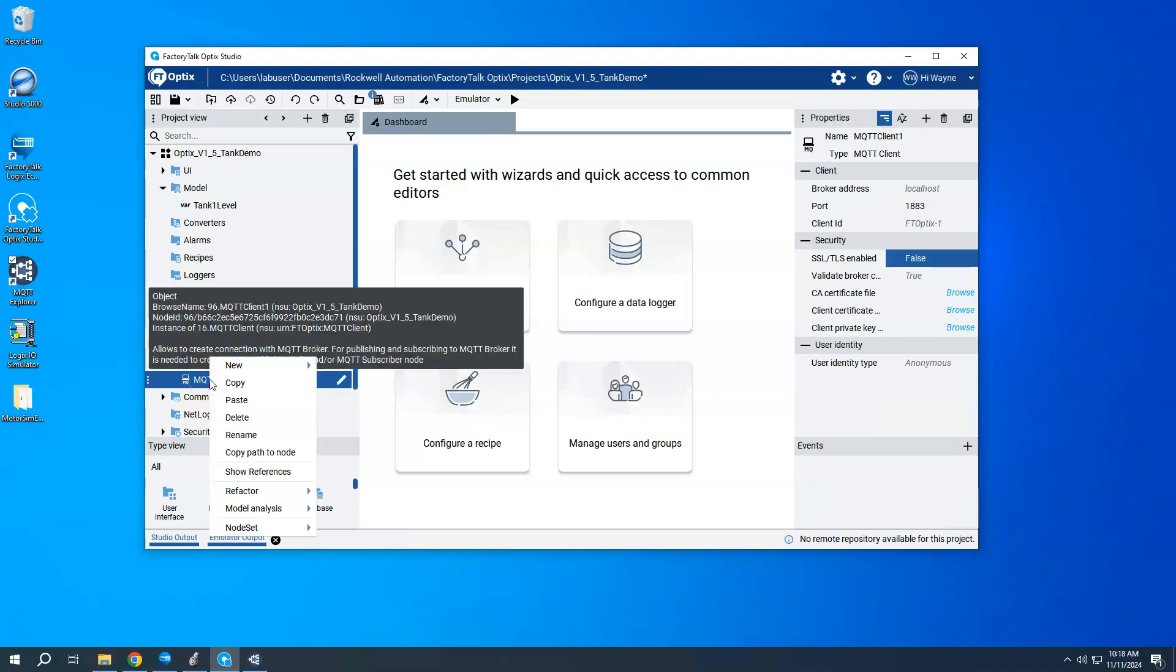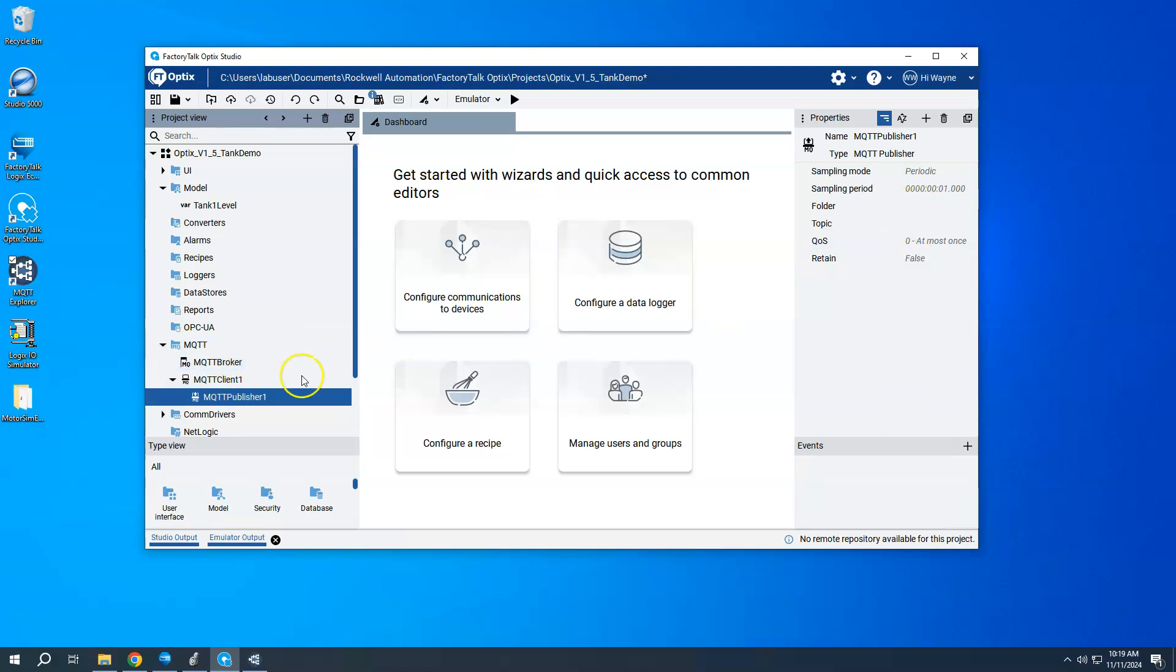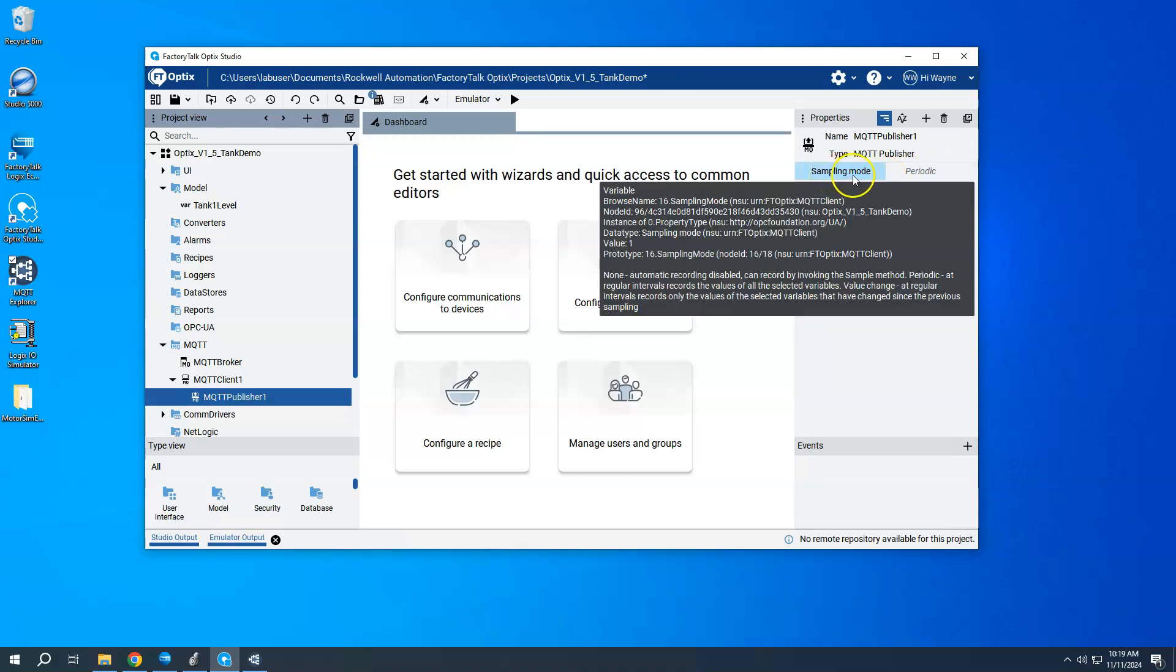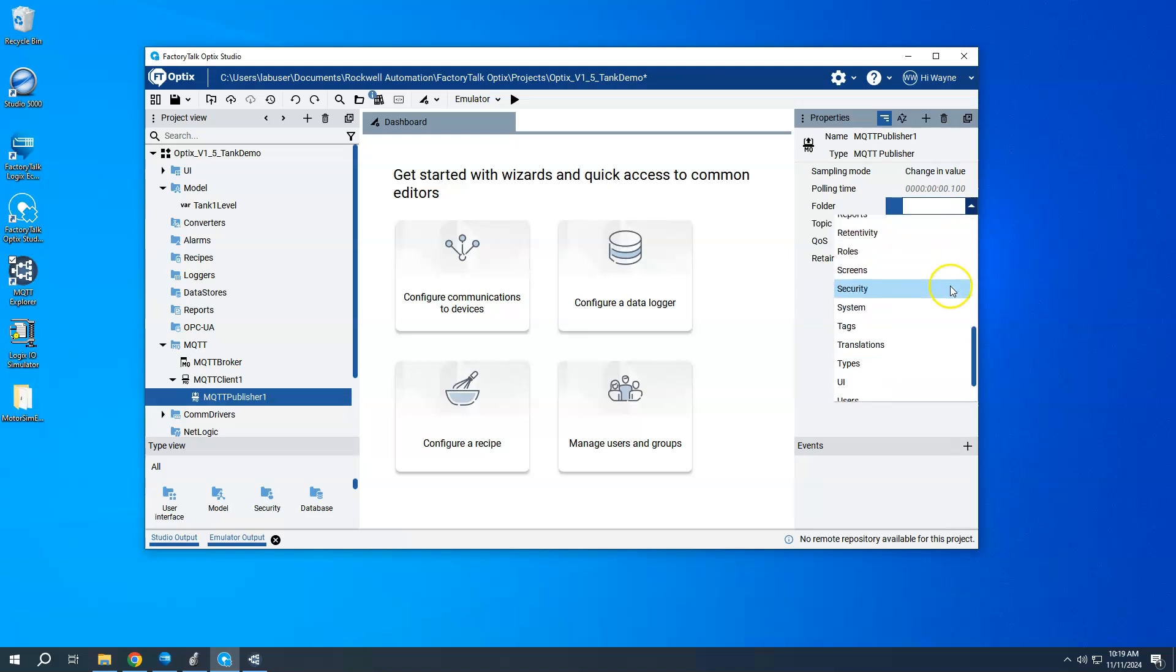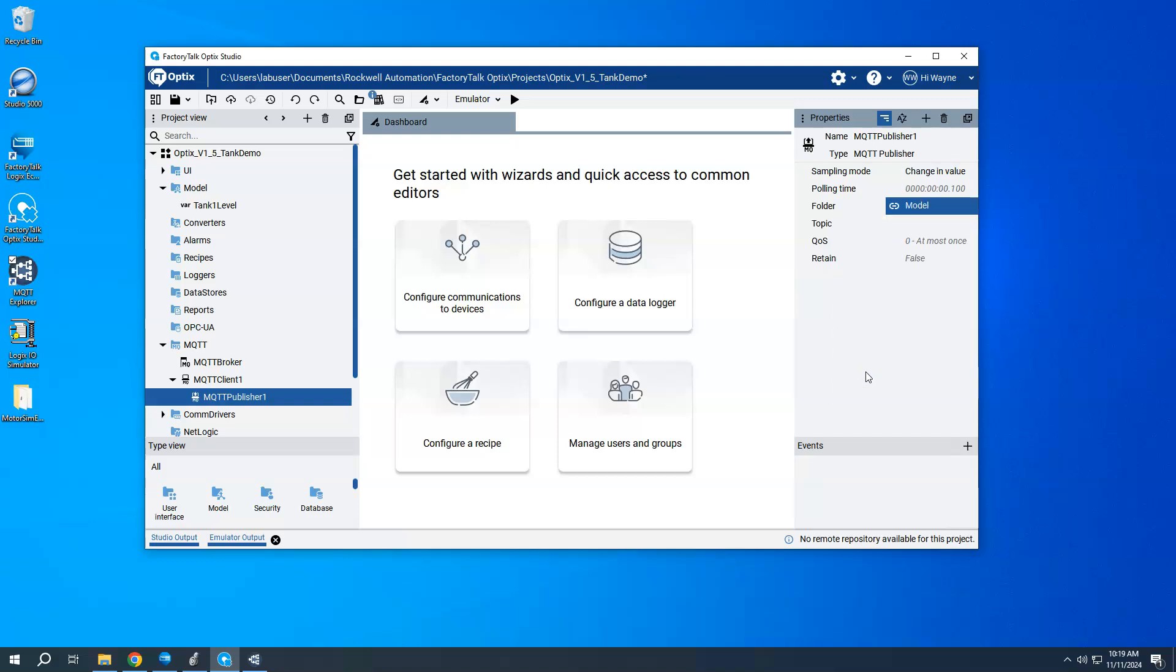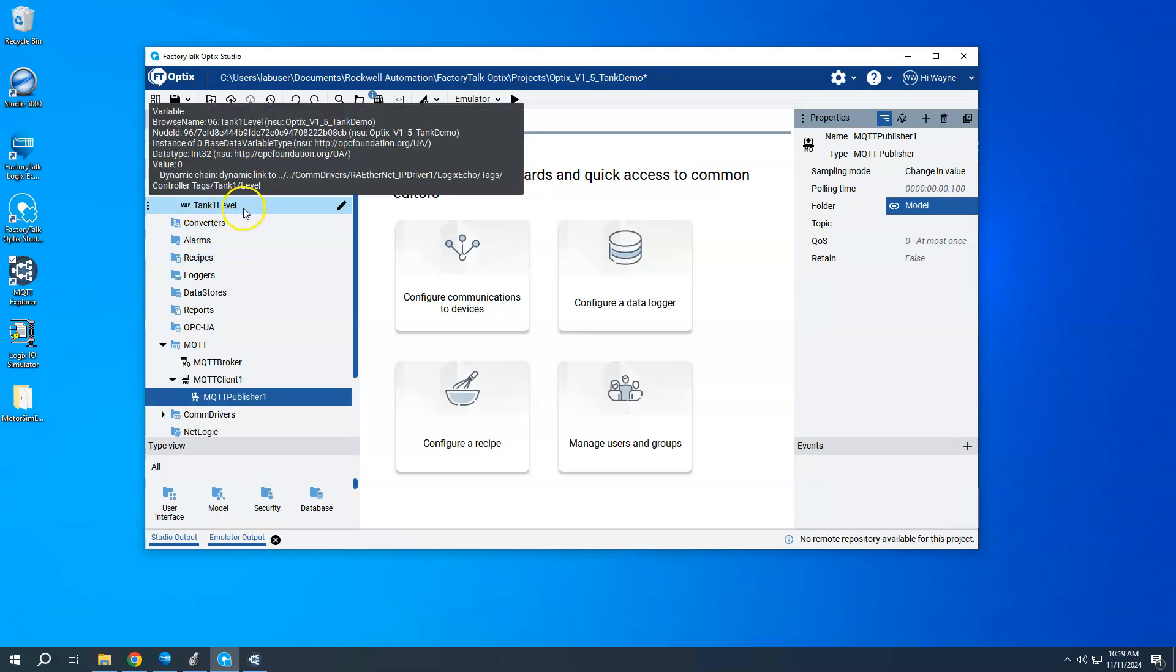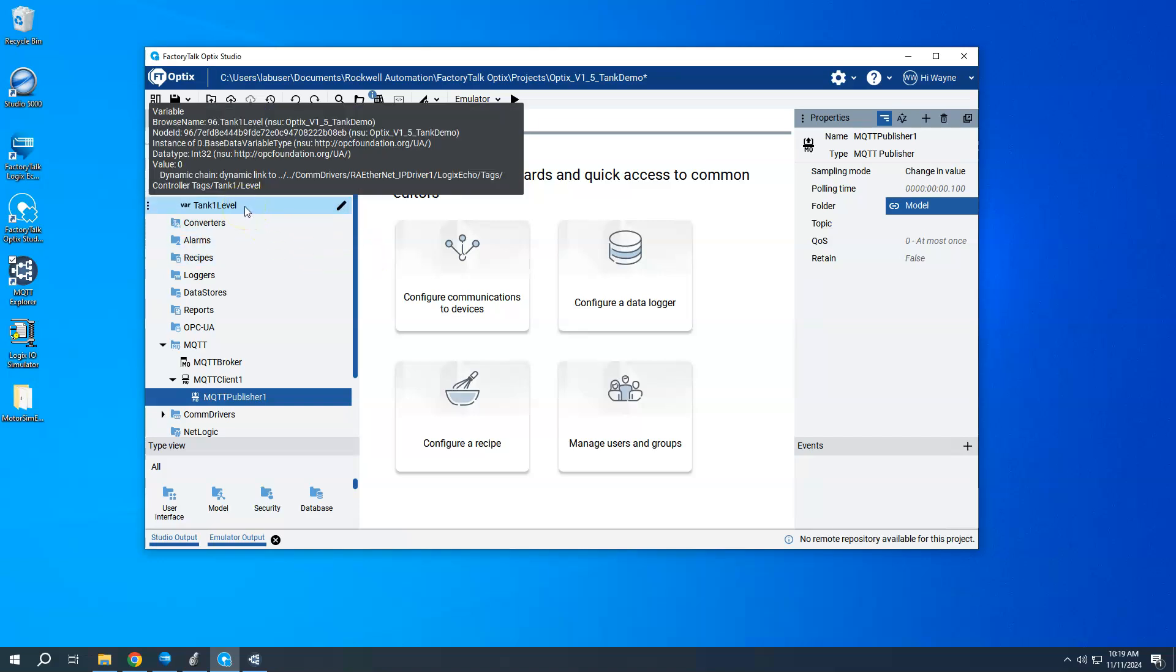Next, I need to basically right click on this client and say, am I going to be a subscriber or a publisher? And in this case, I'm going to publish. I want to publish a tag or a variable that's inside of my Optix application and send it to the broker. So I'm going to use publish. So under publish, we basically have just a few options here, sampling mode. Do you want to be periodic, none, or on change? I'm going to go and say change in value just for this example. Then we have a folder, which is basically going to be, where is the tag? In the application coming from. So the folder that I'm going to use is the model folder. Is what I've done is I've added a tag or a variable underneath the model folder called tank one level.